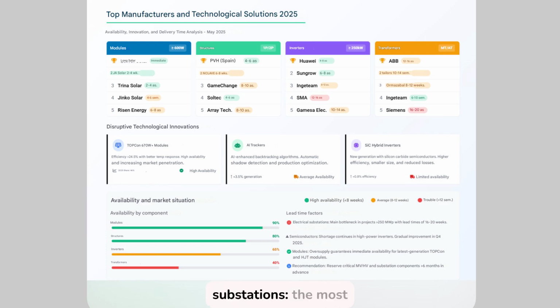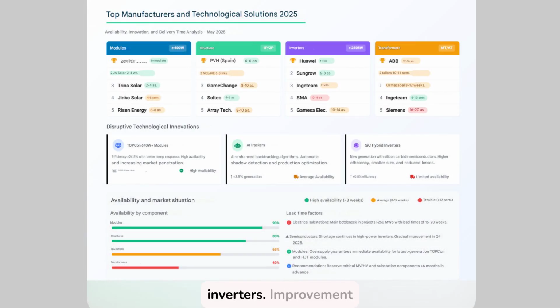MVHV substations, the most serious bottleneck. Lead times can reach up to 20 weeks. Semiconductors, partial shortage of high-power inverters. Improvement expected in Q4 2025. Modules, oversupply due to Chinese expansion, guaranteeing immediate TOPCon and HJT deliveries. Key recommendation: reserve all critical equipment such as transformers, transformer substations, and substations more than 6 months in advance. As you can see, the choice of technology must always be accompanied by a joint availability and logistics analysis. Having the best module or inverter is useless if you can't deliver it on the project schedule.